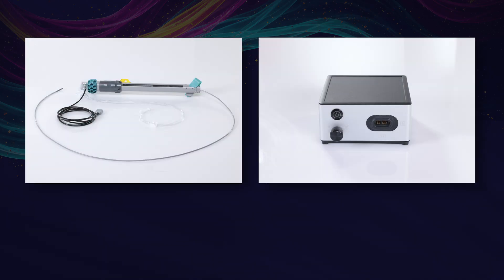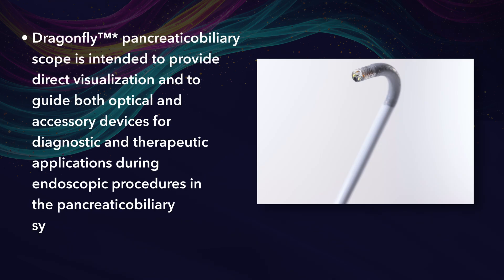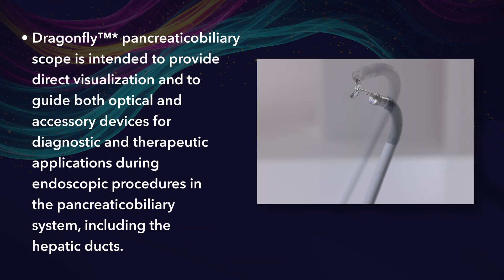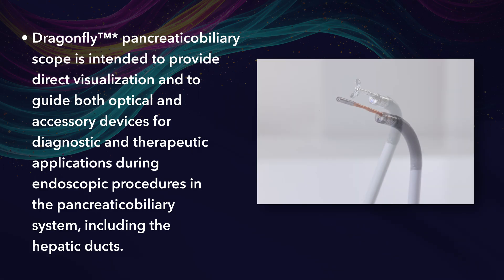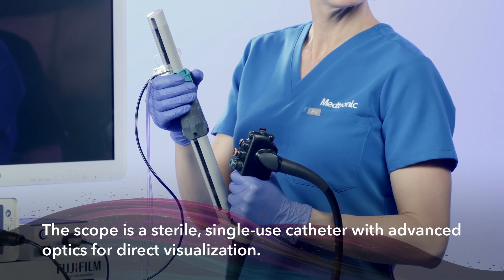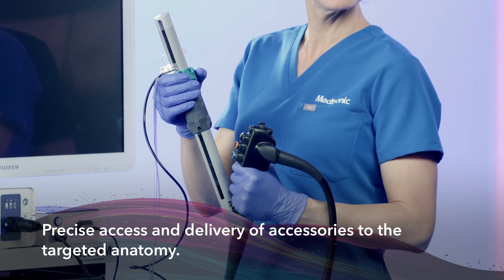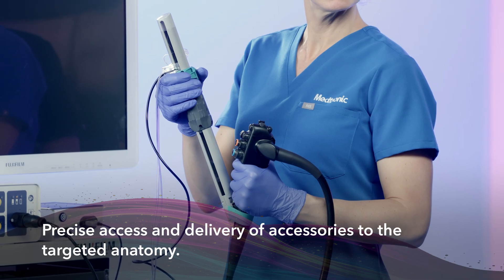Dragonfly System Overview. The Dragonfly System includes two main components: the Dragonfly Pancreaticobiliary Scope and the Dragonfly Digital Controller. The Dragonfly Pancreaticobiliary Scope is intended to provide direct visualization and to guide both optical and accessory devices for diagnostic and therapeutic applications during endoscopic procedures in the pancreaticobiliary system, including the hepatic ducts. The scope is a sterile, single-use catheter with advanced optics for direct visualization, allowing precise access and delivery of accessories to the targeted anatomy.